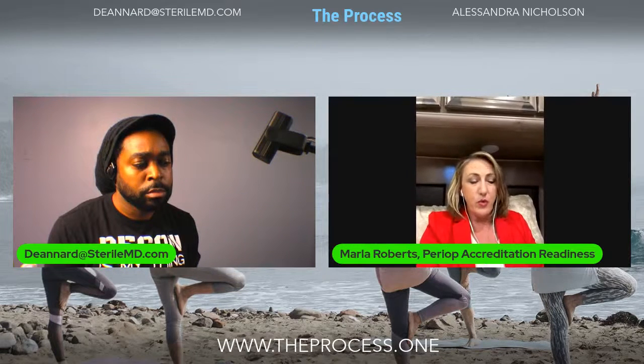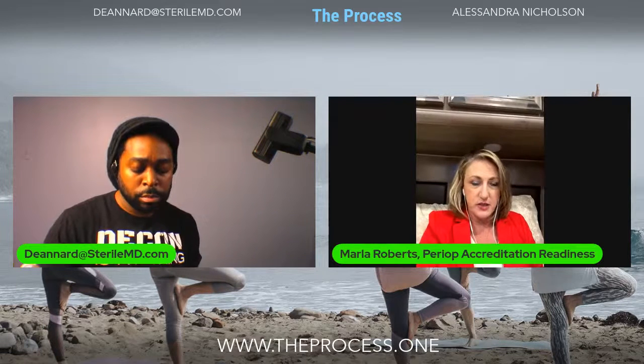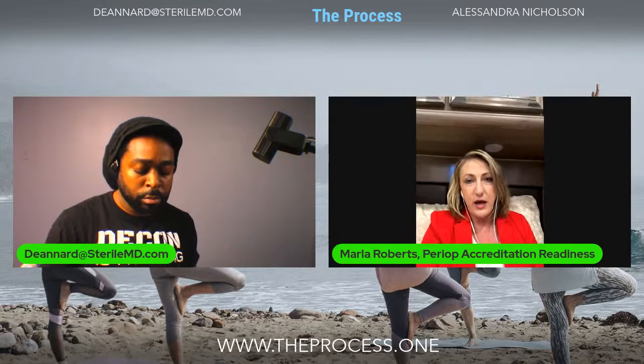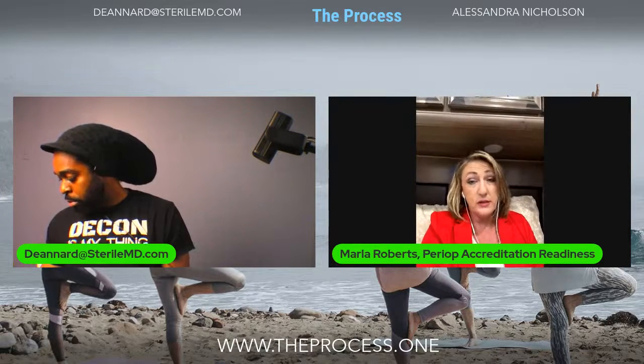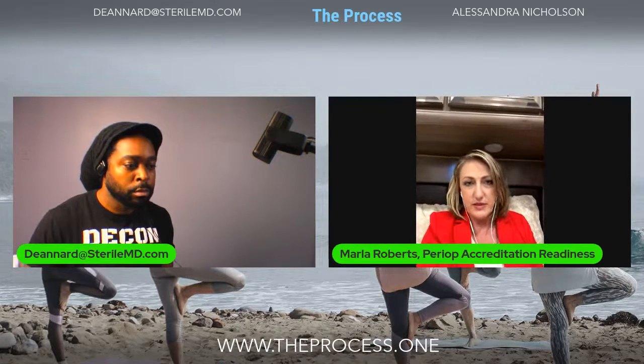And so the number one thing, of course, and it's always a finding for an immediate jeopardy, which means they can shut you down and say, stop your surgeries, stop everything until CMS comes in and lets you kick back up again. And that is your environment of care, doing something in a positive environment that should be negative. So if your prep and pack area is negative, then you're in trouble. And if your decontamination area is positive, then you're in trouble, because it should be the opposite. So it's the same if they go to an operating room, it's always positive, and they read it and it's negative, they will completely go to administration and say, we're finding this as an immediate jeopardy and we need to shut this down. The same thing happened in Detroit, Michigan last year.